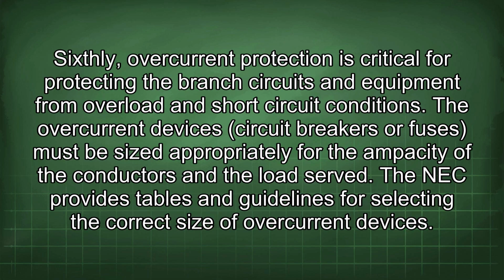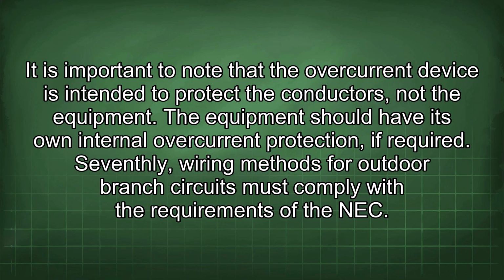Sixthly, overcurrent protection is critical for protecting the branch circuits and equipment from overload and short-circuit conditions. The overcurrent devices, circuit breakers or fuses must be sized appropriately for the ampacity of the conductors and the load served. The NEC provides tables and guidelines for selecting the correct size of overcurrent devices. It is important to note that the overcurrent device is intended to protect the conductors, not the equipment. The equipment should have its own internal overcurrent protection, if required.